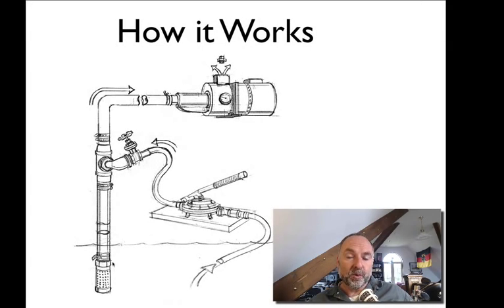Now in order for pumps like these to work, that intake line needs to be completely filled with water. If there's any air in there, even a little, it can stop the pump from working, because water pumps can only pump water.